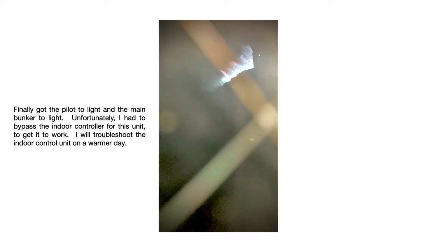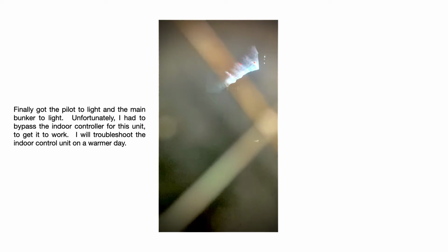And unfortunately, what I had to do was bypass the indoor controller. Basically, there's a box inside the building that has a thermostat, an on-off switch, some other components. Once I bypassed that, as you can see in this clip, the main burner came on. Main burner is lit now.